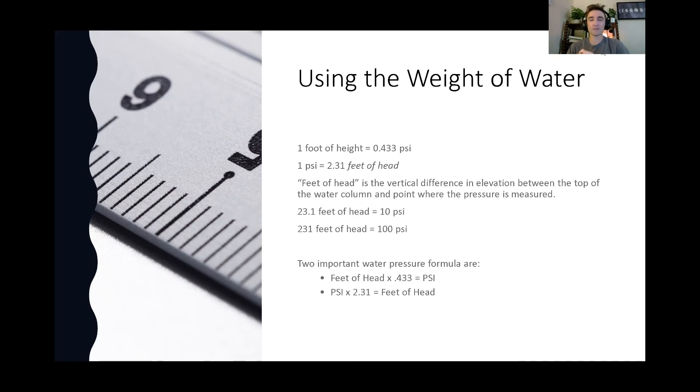So these are the two important factors. And as a formula, you can say the feet of head times 0.433 equals your psi. So if you know how many feet of head you have between you and your irrigation source, you multiply that by 0.433 and that's your pressure. Alternatively, if you know your pressure, you multiply that by 2.31, that gives you your feet of head. How high above you is the column of water.